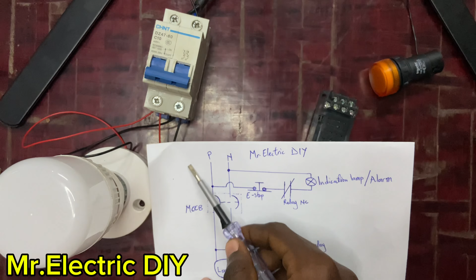Well, you're supposed to connect a cable from this side to the emergency stop, and this emergency stop here is normally closed, and this relay terminal, the normally closed terminal too, is also closed, so current will directly flow from here to the lamp if there is power here. So you have to make sure that this section is being turned off, or the incoming power is turned off. Now we are done connecting the phase from this side to one side of the emergency stop push button.